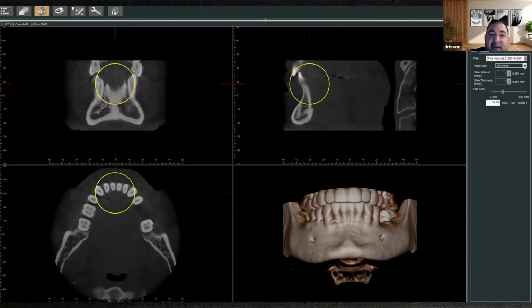So I select that area, and now I'm going to choose the voxel size that I am going to use. As I told you before, Morita has the ability to go even below 80, right? So this could go to 20, but the vast majority of you will see 80 here. So we're going to click 80 on that case, 80 microns. Then I typically change my slice thickness and my slice interval to the minimum voxel size possible, which in this case will be 80 microns, for 1-1. Just keep it a 1-1. And then all I have to do now is hit the button run.